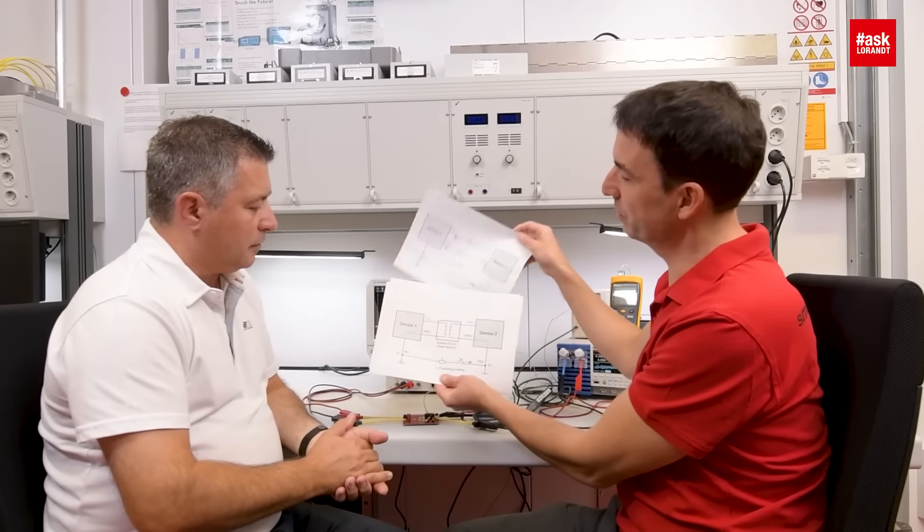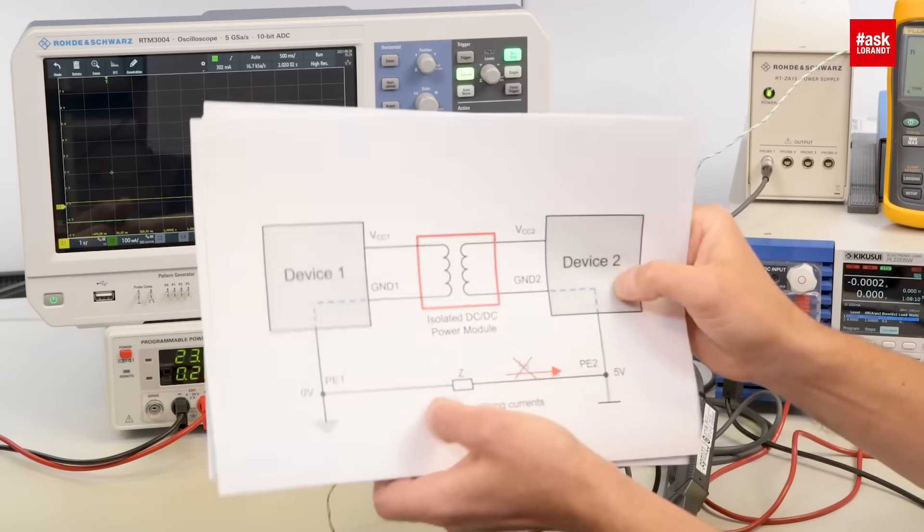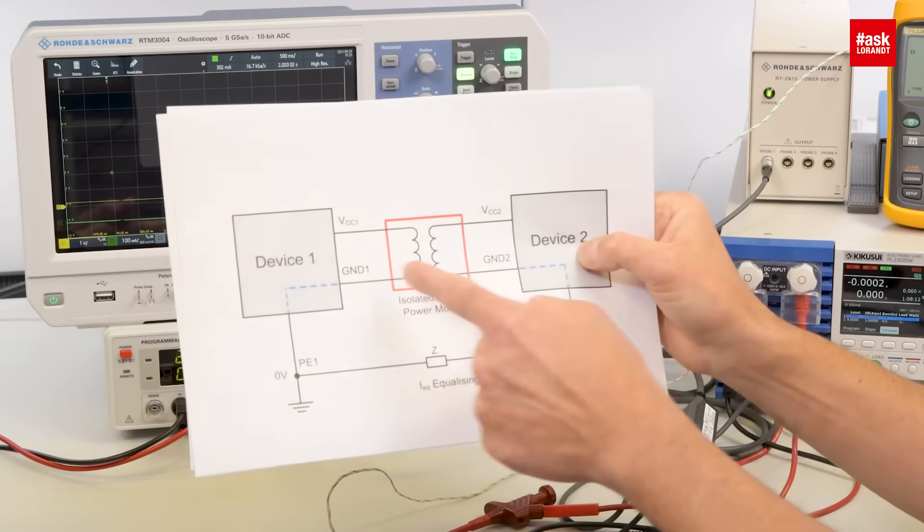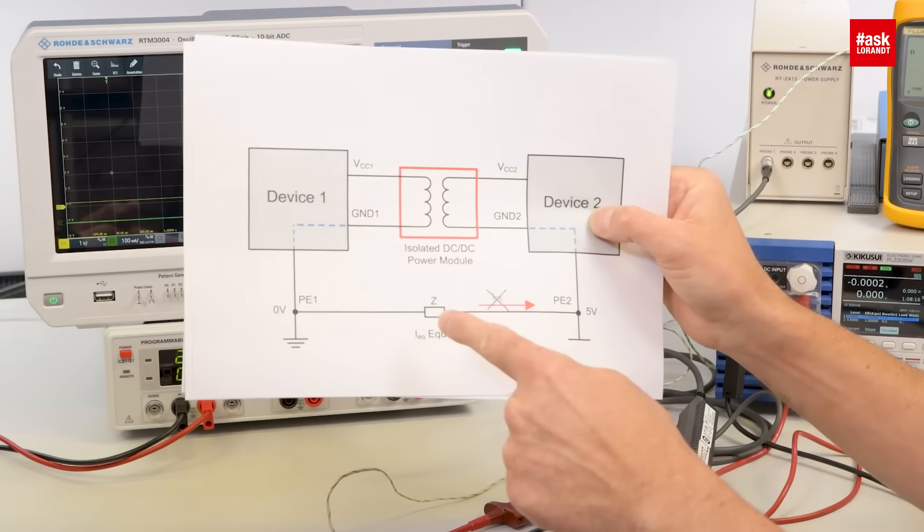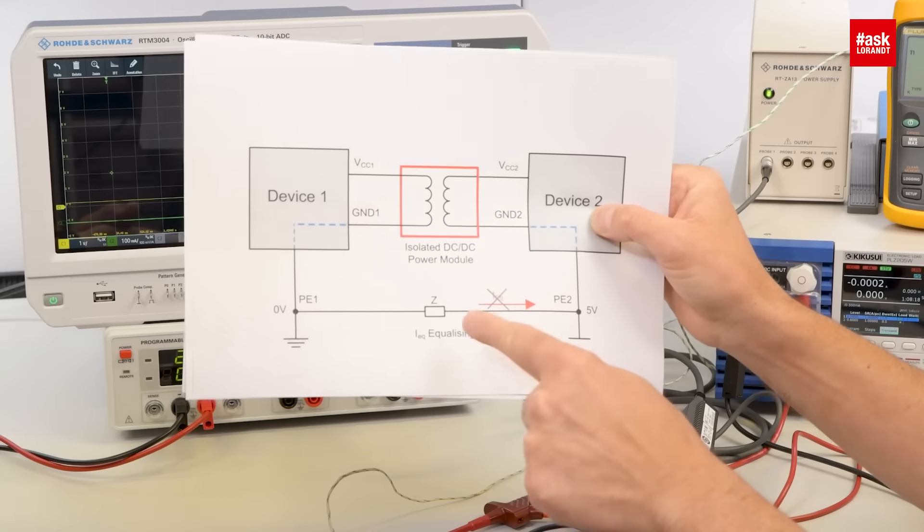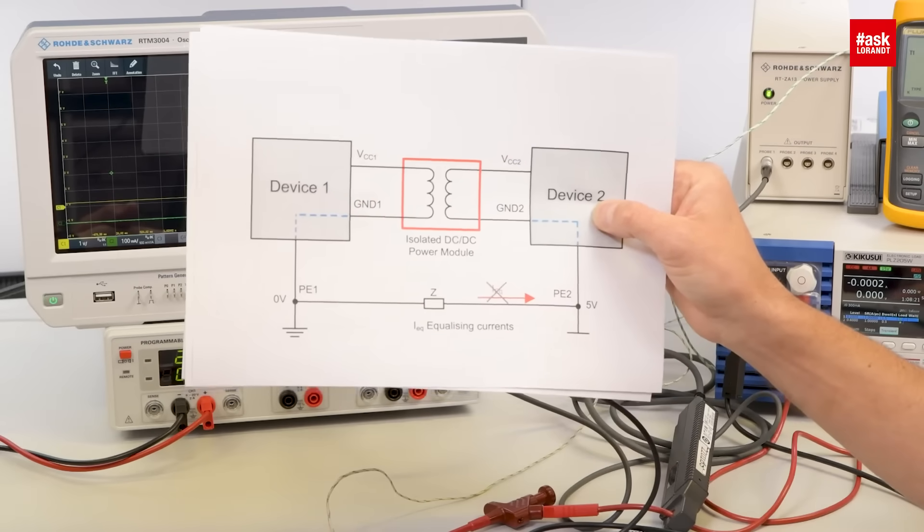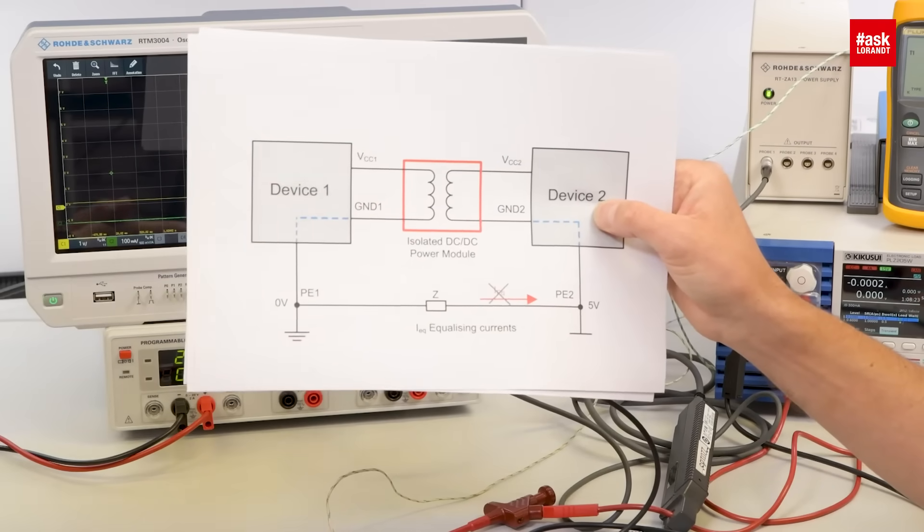And what you can do to get rid of this disturbance, you can take a MAGIC power module here so that you break up the ground loop so that you have got the impedance but it is not possible that an equalizing current can flow. So perfect communication.